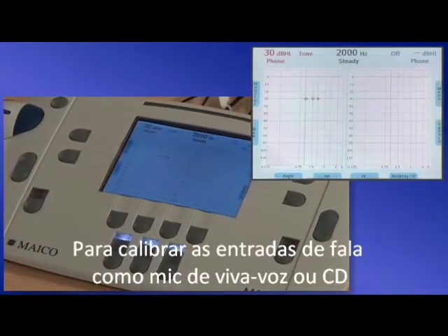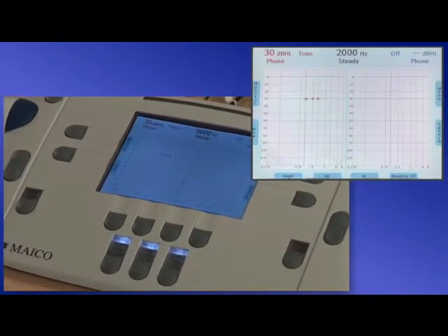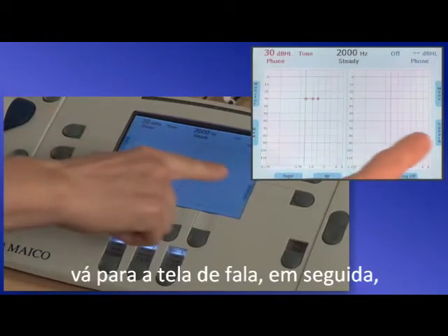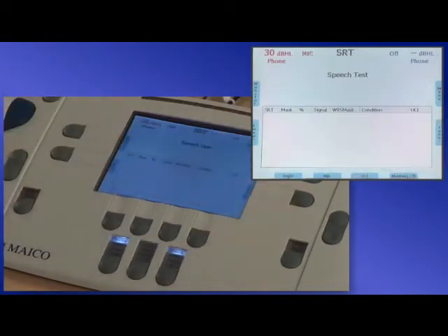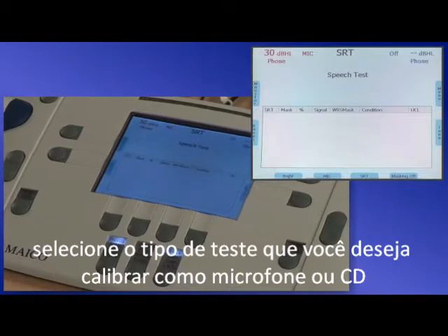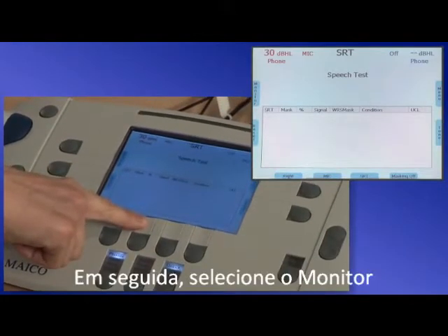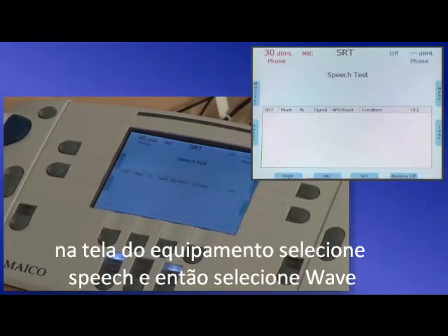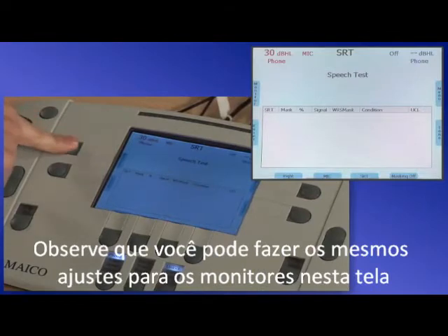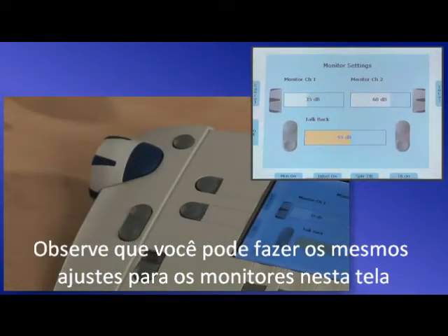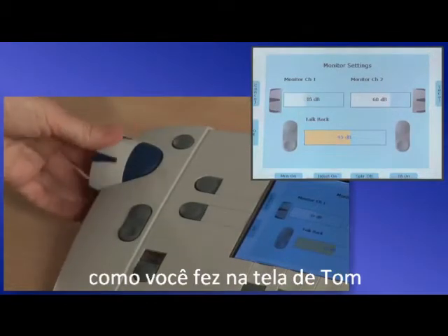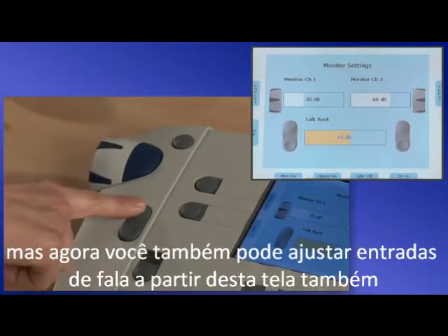To calibrate speech inputs such as live voice mic or CD, go to the speech screen. Then select the type of test you want to calibrate, such as mic or CD. Then select Monitor. Notice that you can make the same adjustments to the monitors in this screen as you did from the tone screen, but now you can also adjust speech inputs from this screen as well.